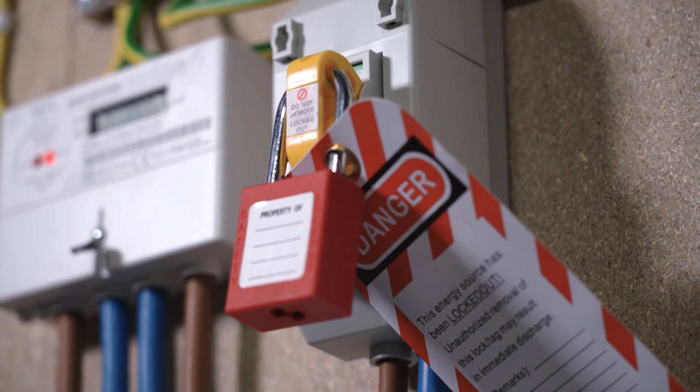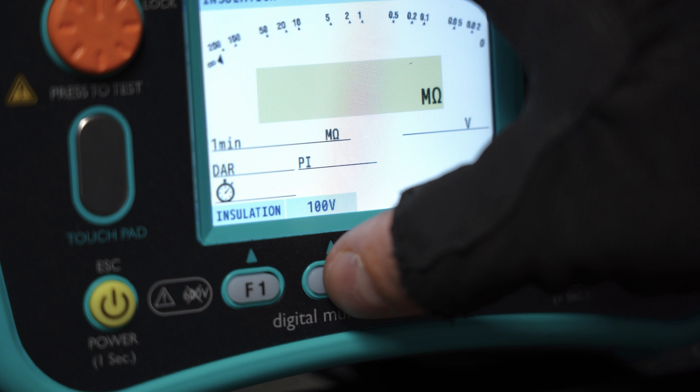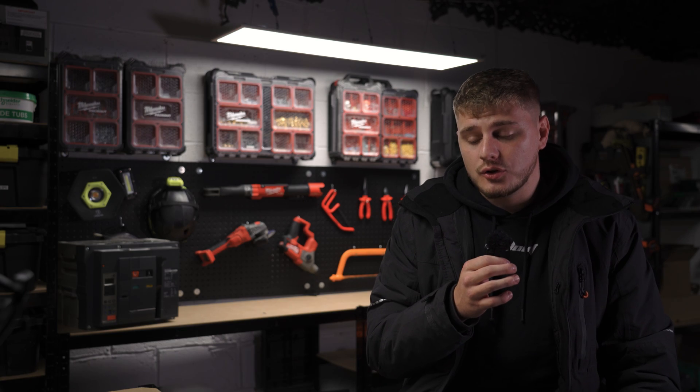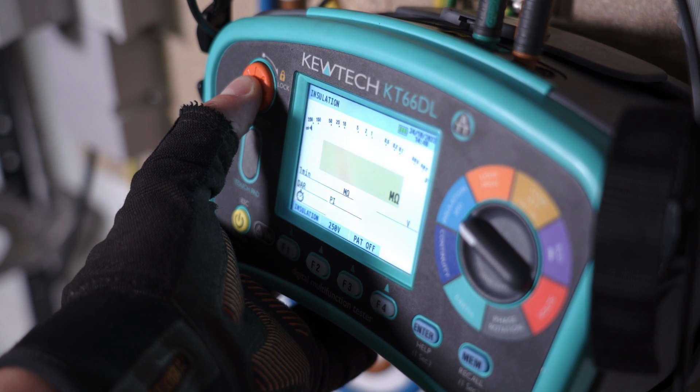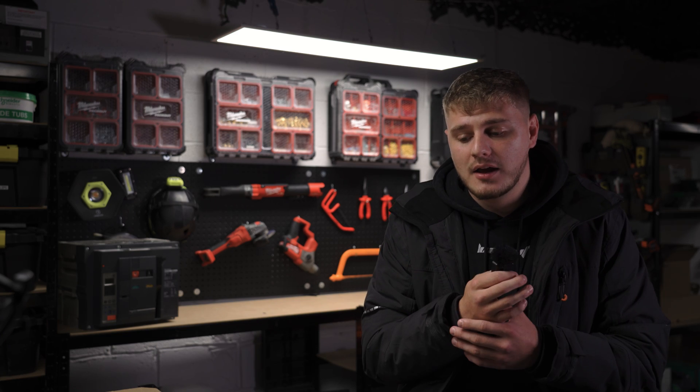Before we get into anything, this is a dead test so the installation should be isolated. On a new installation this is carried out as part of the initial verification process, but on an existing installation you'll need to carry out the safe isolation procedure. However, the test does create live conditions — you're firing a voltage through the circuit: 250, 500, maybe even 1000 test volts. Notify people within the installation and co-workers about what you're doing and what not to touch.